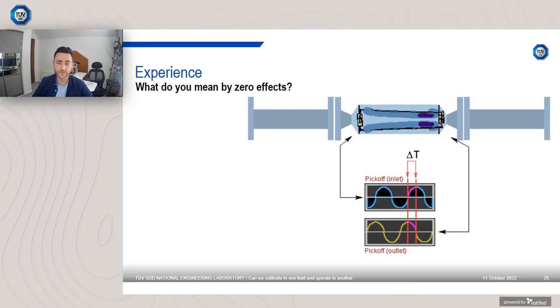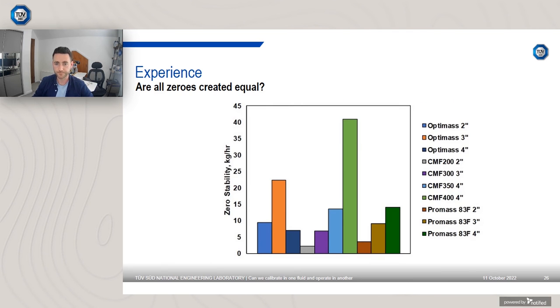Now that's the ideal scenario. However, in most scenarios, what actually happens is you still get some zero effects. And down below around about 5 to 15% of a Coriolis meter's flow range, you sometimes do get the effect of zero, depending on how significant the zero effects are. So I've got some examples of that. That's just a calculation for it there.